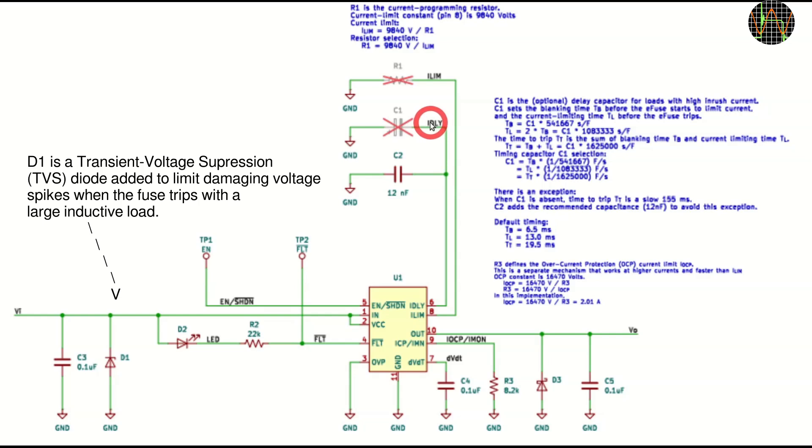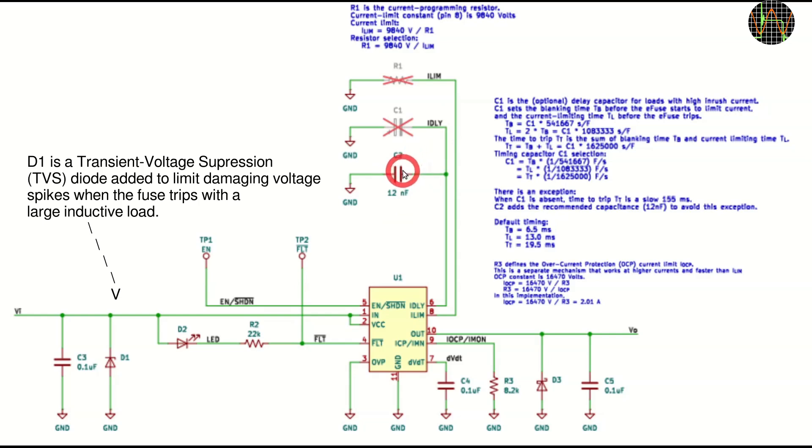The capacitor determines the blanking time from which the current limiting time and the total time to trip are determined. With C2 of 12nF, the PCB provides a default which results in a blanking time of 6.5ms, a current limiting time of 13ms resulting in a total trip time of 19.5ms.